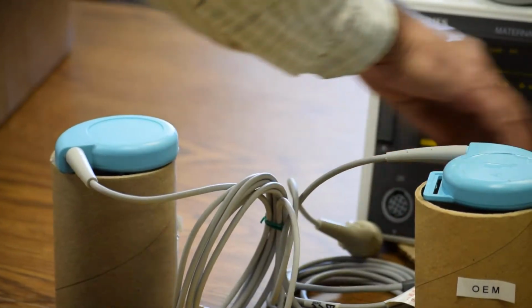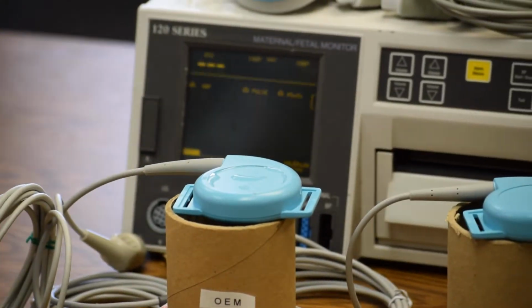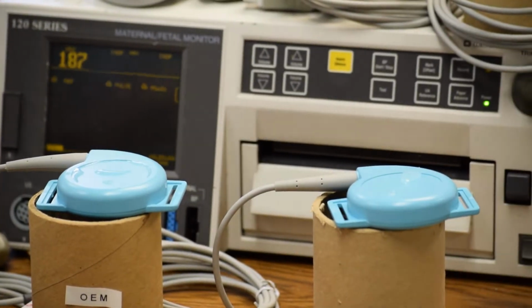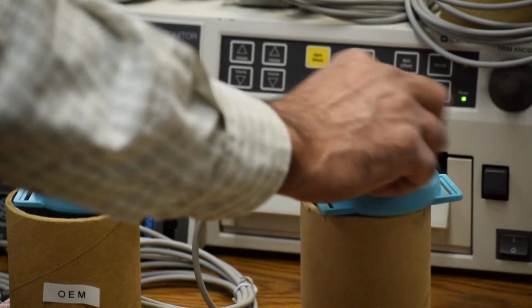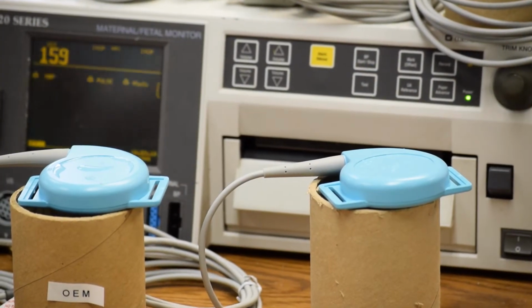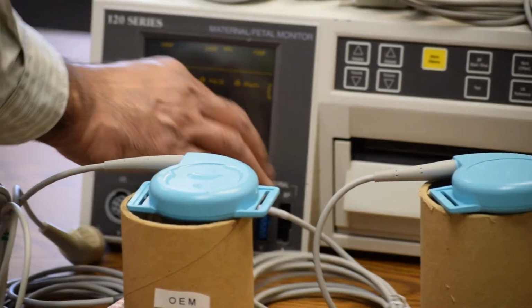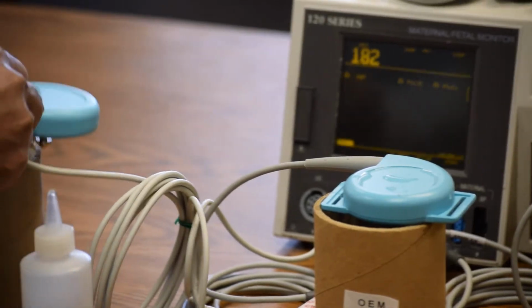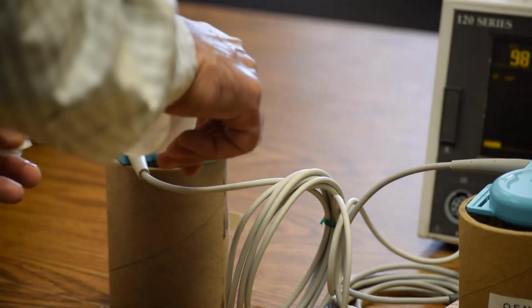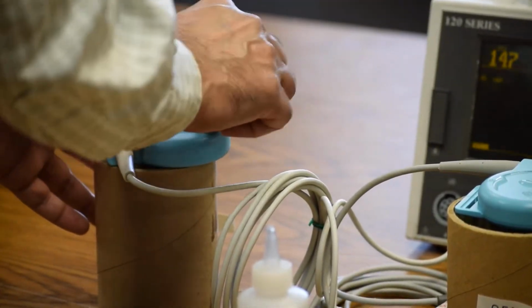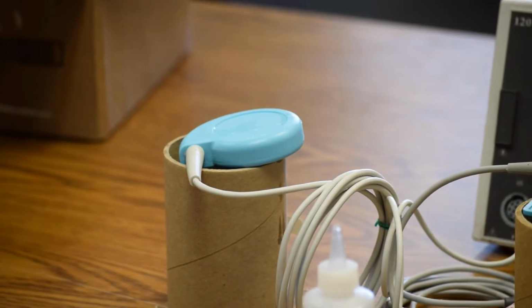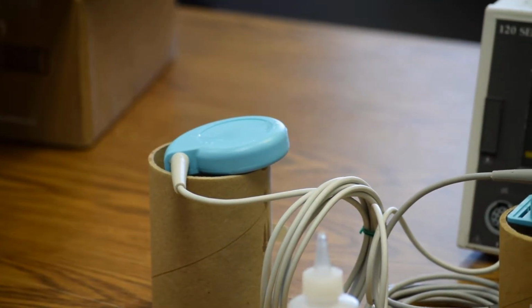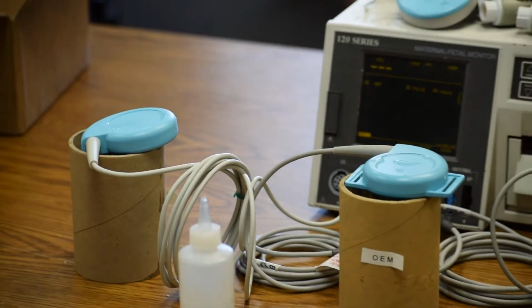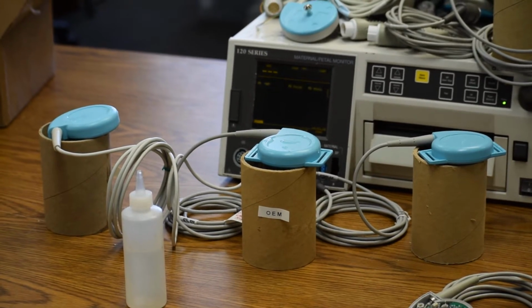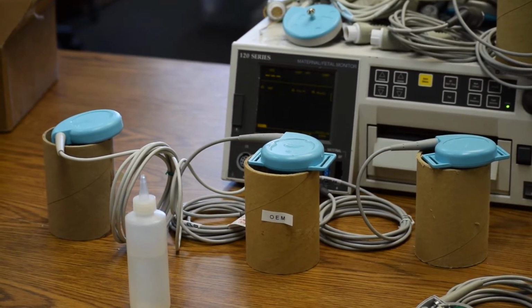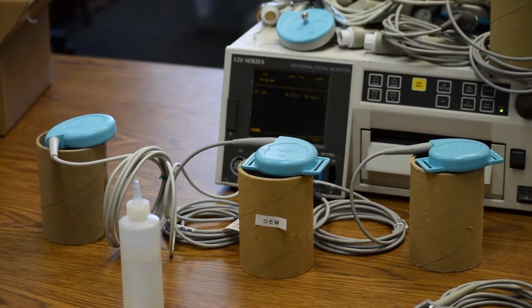Let's compare with another original GE transducer. Same level of testing, very low volume. Again, recheck the same socket. Let's pour a little bit more water. So the echo signal is very poor, very low volume that you get, because the non-OEM crystals gluing process is non-compliant. There is absolutely no work in line with GE specifications.